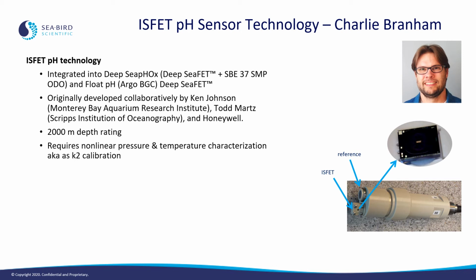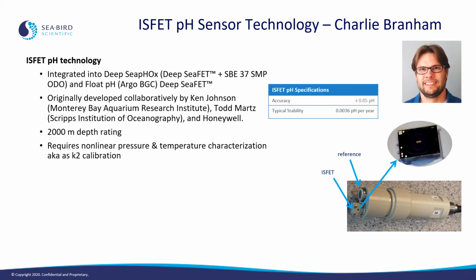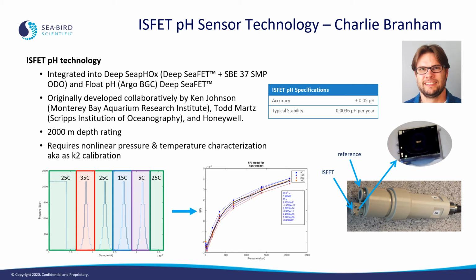It does require very involved nonlinear pressure and temperature characterization of the actual ISFET chip. And when you do that, you typically can achieve accuracies of about plus minus 50 millipH and a stability of a few millipH per year. But even with that characterization, you have large temperature and pressure offsets over the whole pressure range, and also a very nonlinear response of the sensor near the surface. So it's very difficult to model, and our yield in manufacturing as a result of that is actually quite low.